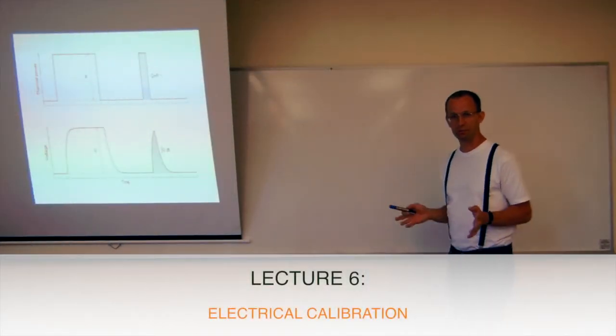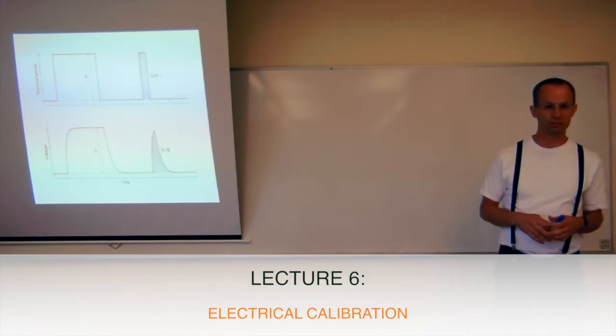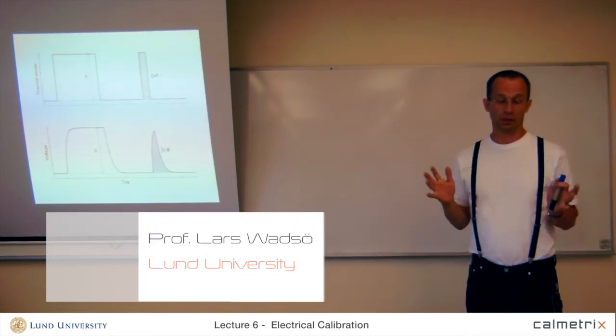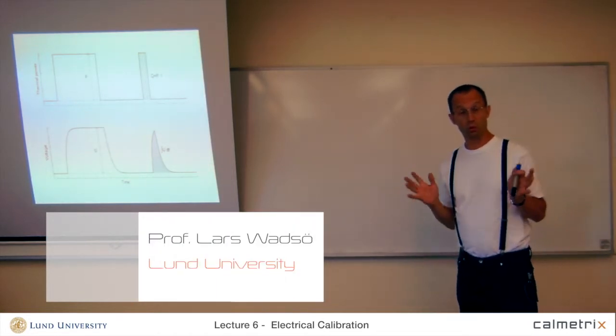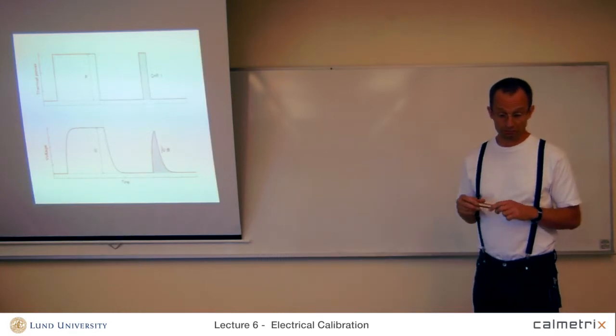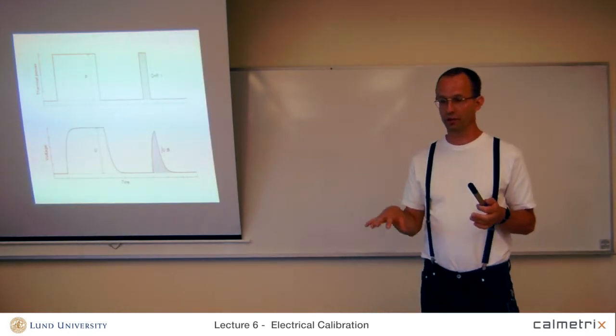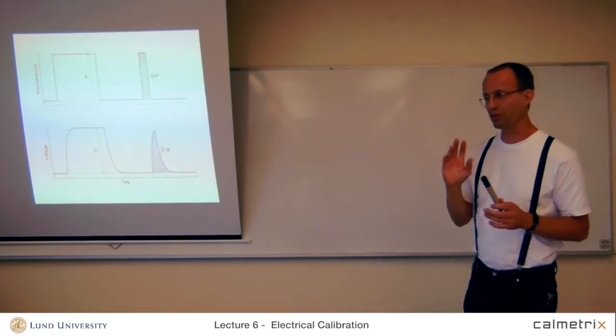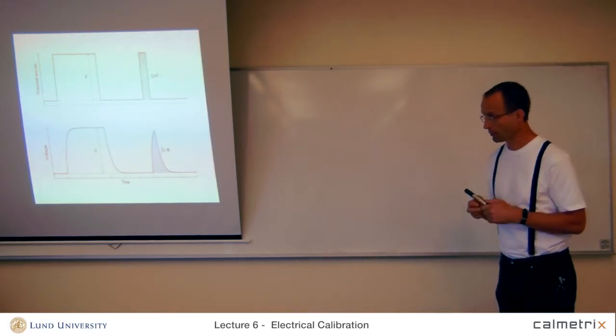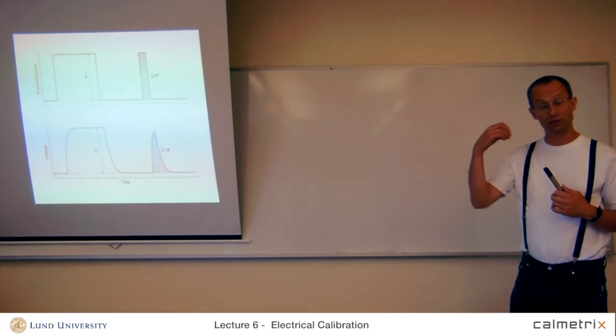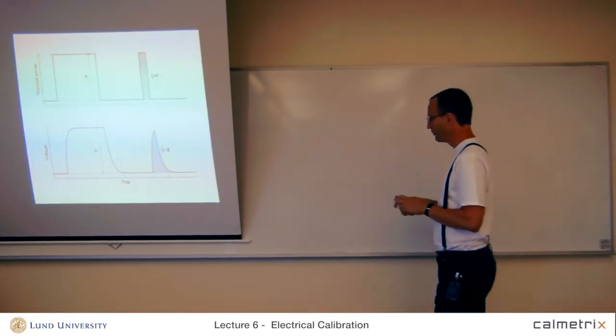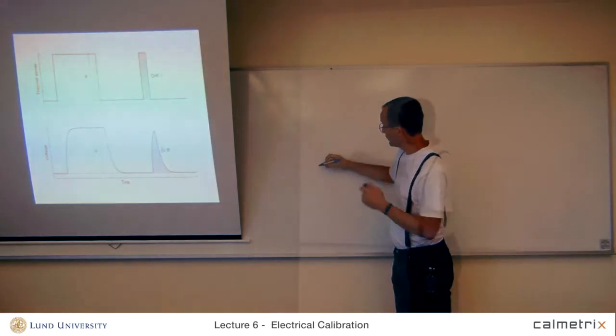The most common way of calibrating isothermal heat conduction calorimeters is electrical calibration. This is easy, convenient and quick. So, this is the normal way that calorimeters are calibrated and this is done by placing a heater in the calorimeter or in the sample or close to the sample and passing an electrical current to the heater producing heat.